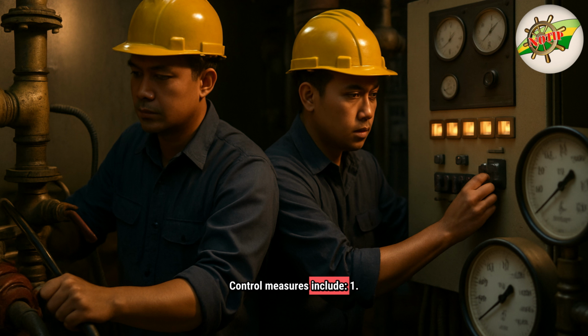Control measures include: 1. Reducing boiler load. 2. Stopping the burner safely. 3. Maintaining forced draft to prevent backflow of flames. 4. Closing air registers only as per recommended procedures. 5. Never opening manholes or access doors while the uptake is hot. Routine soot blowing, proper burner maintenance, and combustion monitoring are key preventative practices.